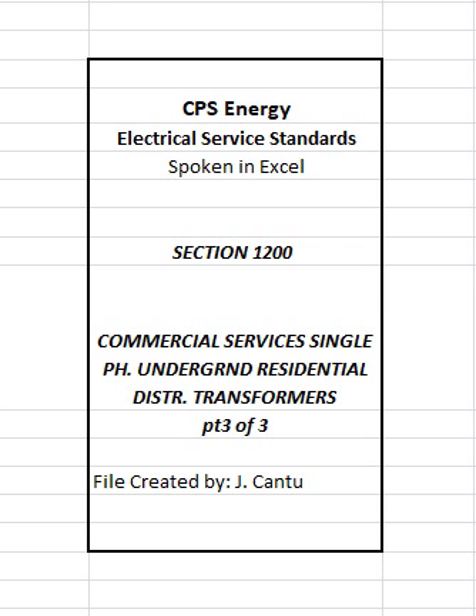5. Where required by CPS Energy, an oil containment pit shall be constructed by customer in accordance with specifications provided by the CPS Energy Customer Service Representative. Oil containment pits are required where oil capacity exceeds guidelines established by the Environmental Protection Agency, EPA, or the Texas Commission for Environmental Quality, TCEQ. Note: standard transformers and pull boxes shall be mounted on a precast concrete slab provided by CPS Energy.